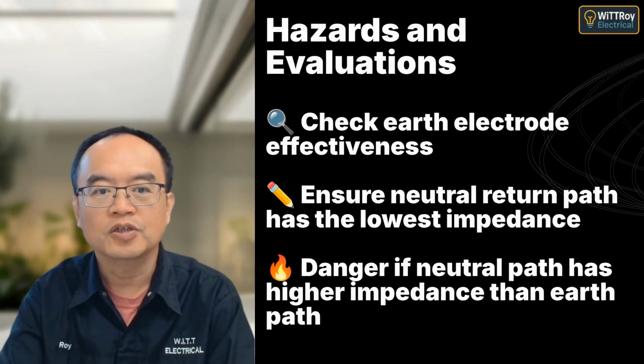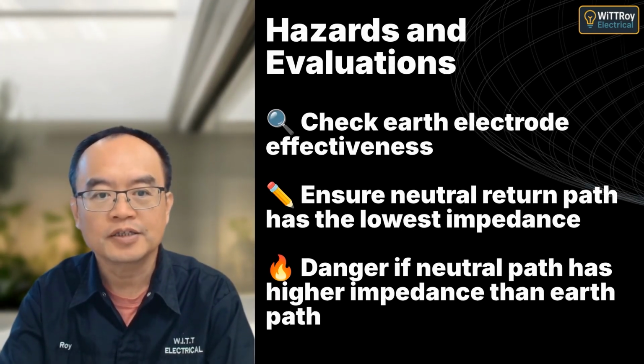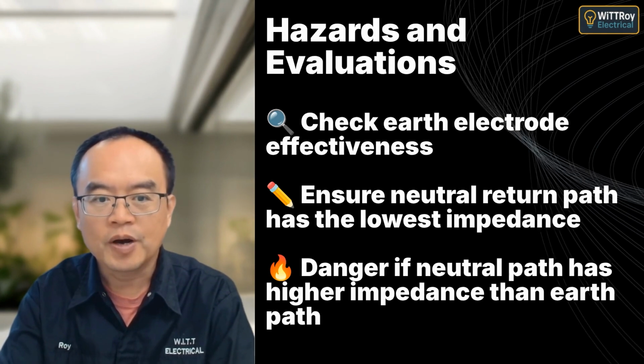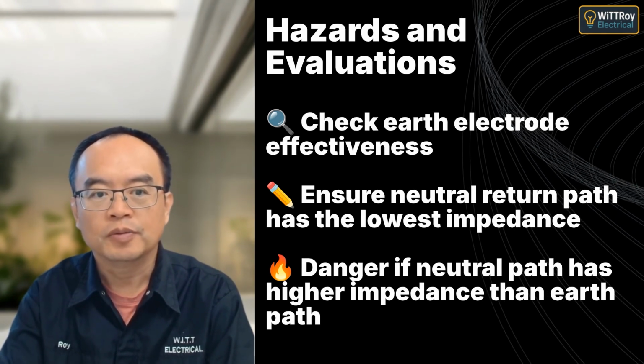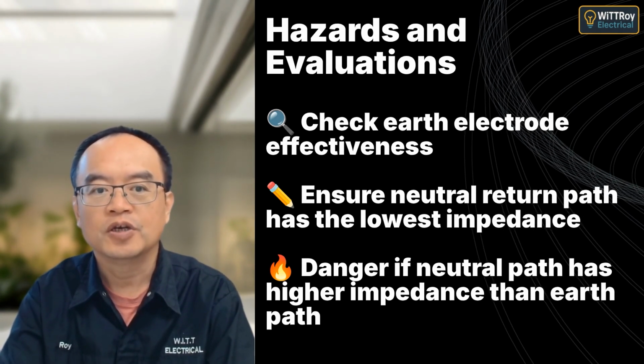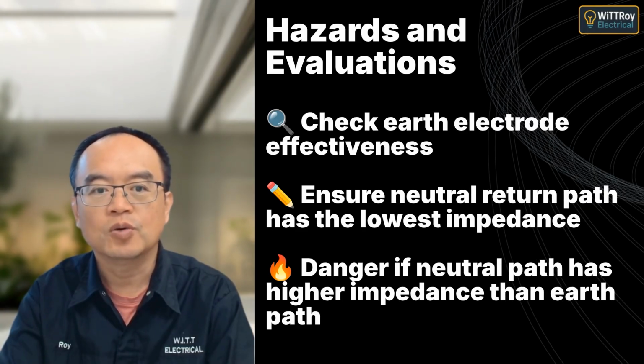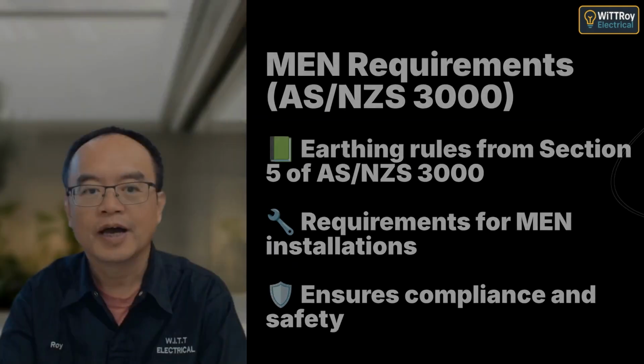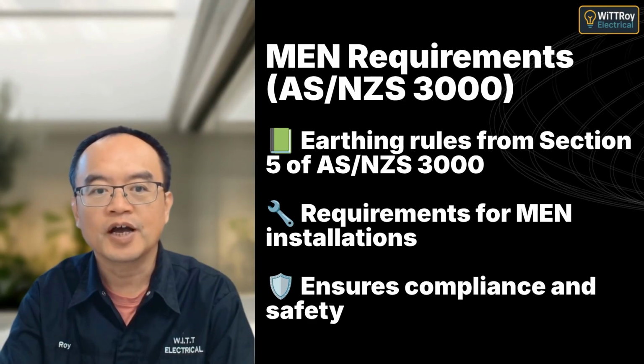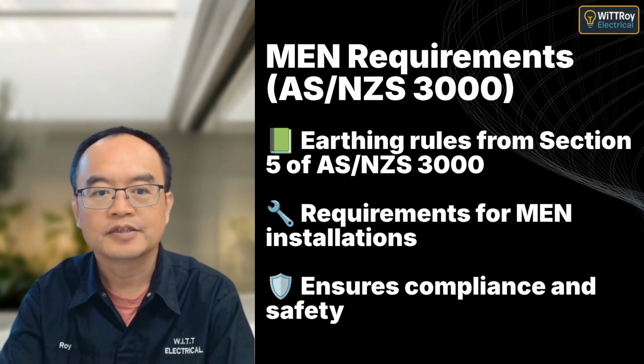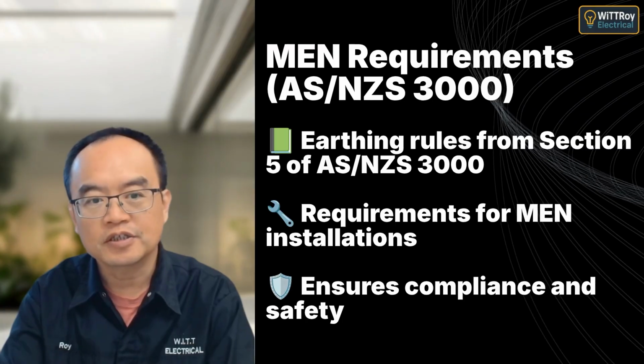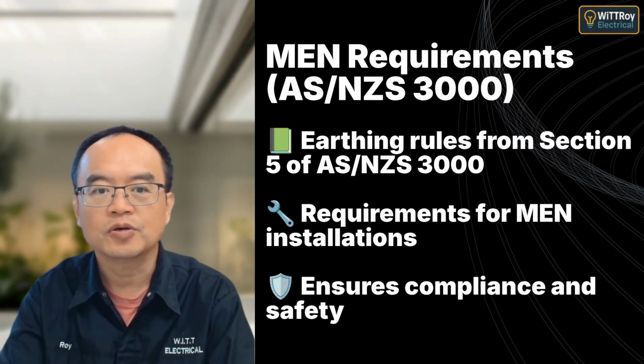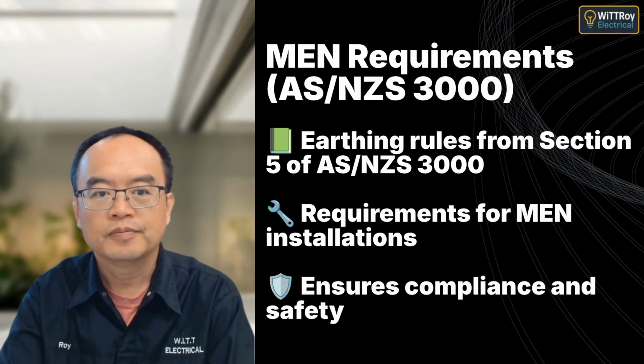Always check that the earth electrode is effective and that the neutral return path has the lowest impedance. If the neutral path has higher impedance than the earth path, current may flow through the earth instead. This can cause serious safety risks such as electric shock or fire. AS/NZS 3000 Section 5 outlines strict earthing requirements for MEN installations. Adhering to these standards ensures installation safety and compliance, protecting people and equipment. Great work, everyone. That covers MEN systems thoroughly. Next, let's apply this knowledge in some Moodle questions to reinforce your understanding.